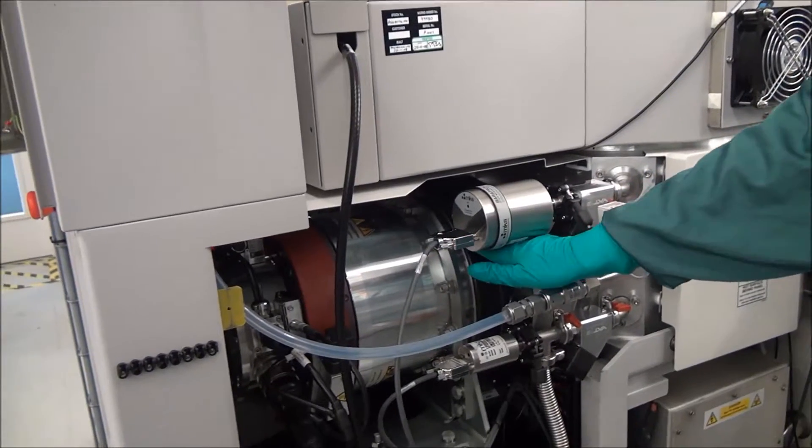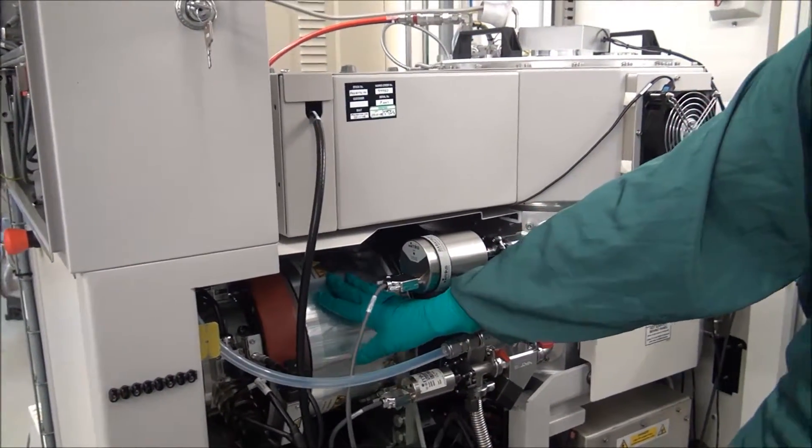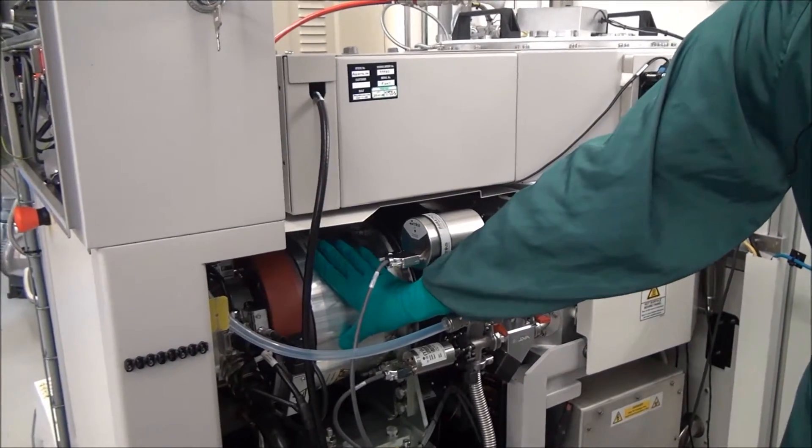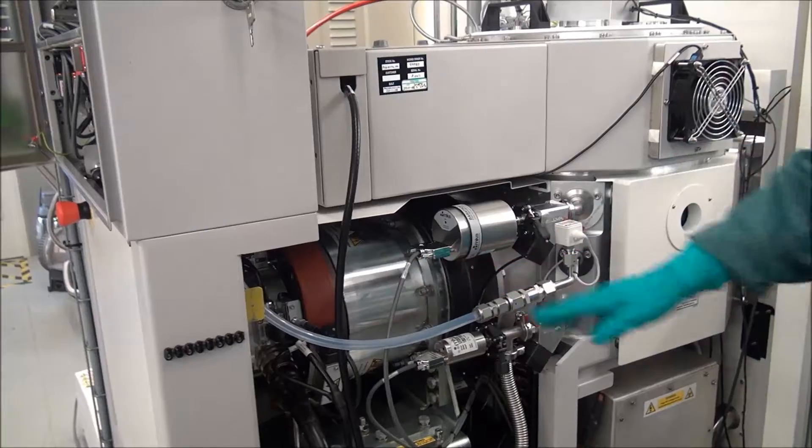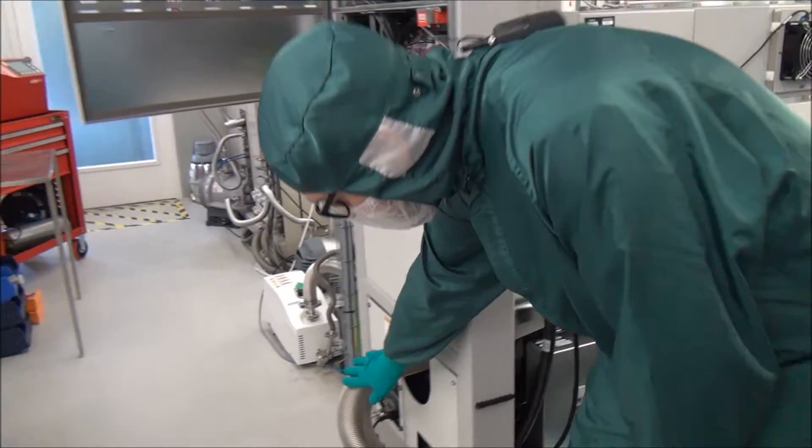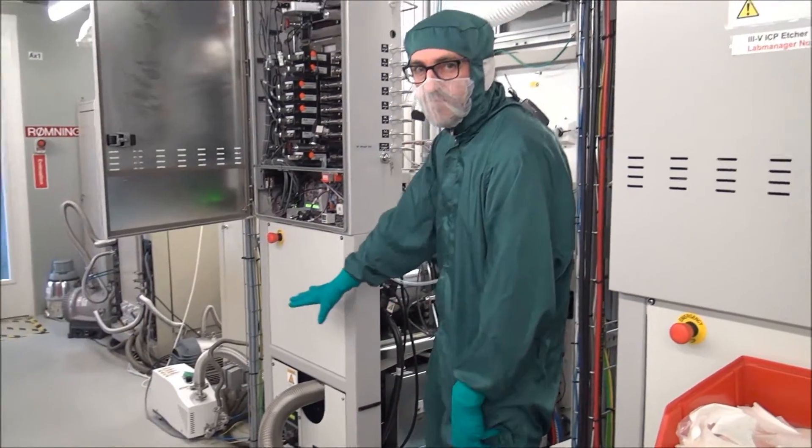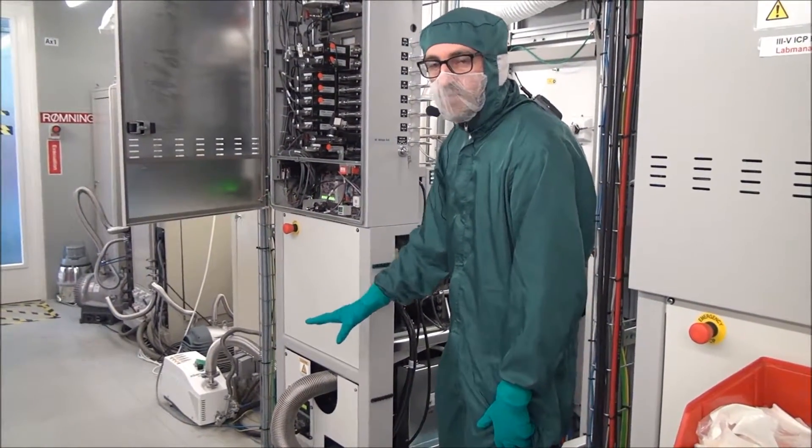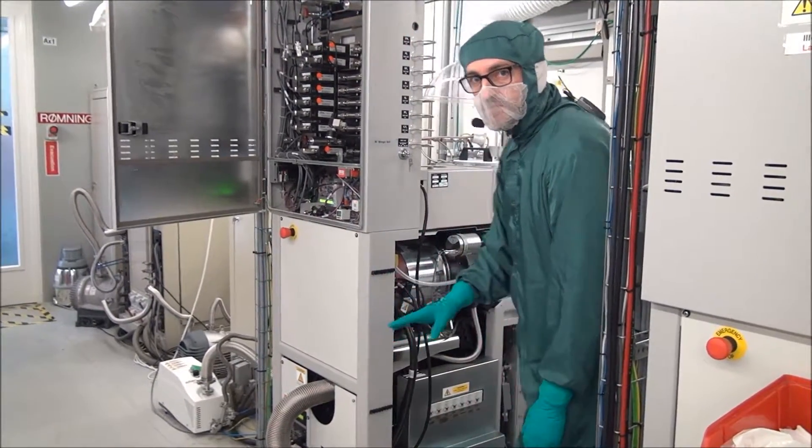Behind the main pressure controller we have a turbo from Leybold which is also heated because of the corrosive gases. And then if we follow behind the turbo you can see here we have a pump line which is actually roughly 10 meters in length. It goes into the basement where we have another backing pump located there, and a scrubber of course because of the gases.